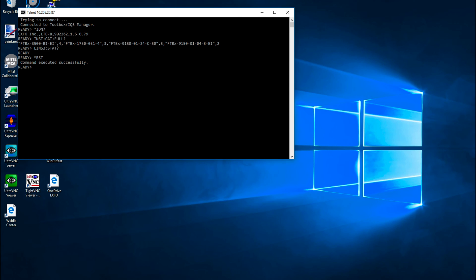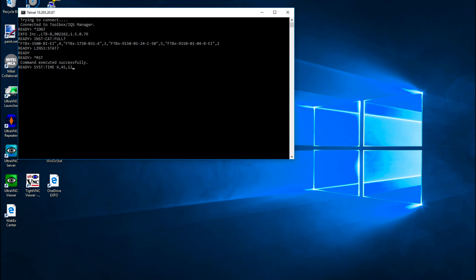Finally, commands and queries can be specified using parameters. For example, if we wanted to change the time on the instrument, we could send the following command from the controller, which would set the time at 9 hours 45 minutes 12 seconds AM.